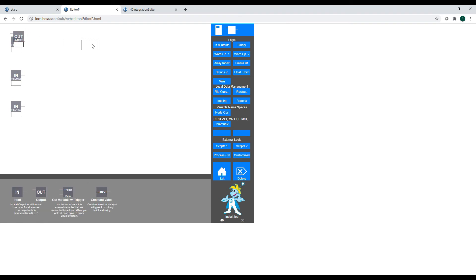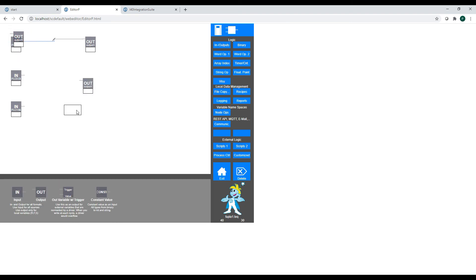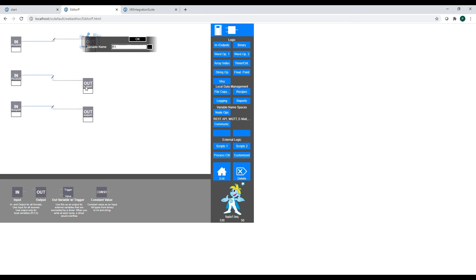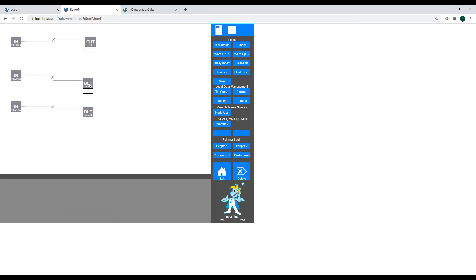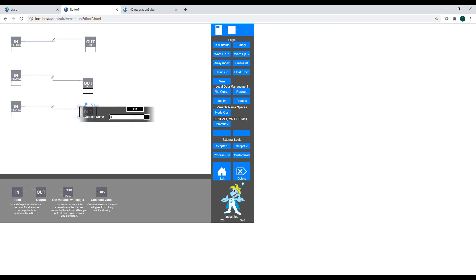We will send this to some local variables. So we will connect this to outputs. The Spider PLC contains some internal registers. So we will just copy our first variable to register 1. Registers called R and the number are 32-bit integers. Copy that to R2 and this to R3.